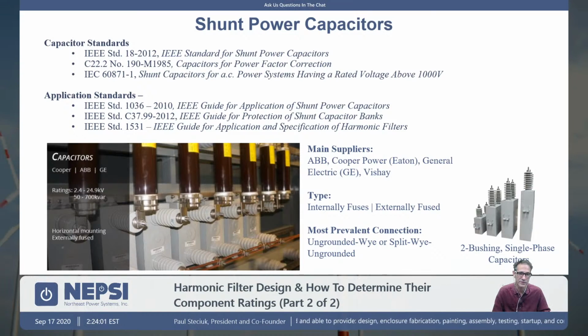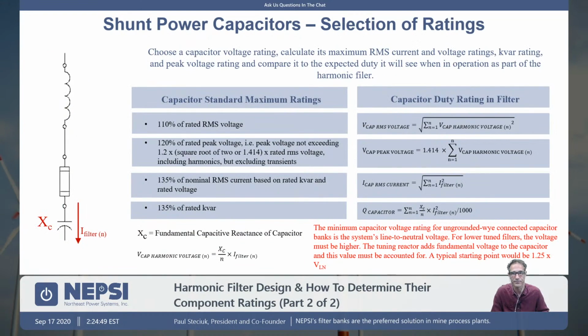The most prevalent connection for medium voltage, 2.4 kV through 38 kV, is an ungrounded Y capacitor bank, or an ungrounded split-wye capacitor bank. We won't really get into too much of what the difference between a split-wye and an ungrounded Y is, but they're both ungrounded, and that's really the key here. You would typically not want to connect a medium voltage capacitor to ground because it's introducing the zero sequence network into the system, and that's a more complex network. With your filter design, you'd now be dealing with the zero sequence network and the positive sequence network. So if we don't connect the filter bank to ground, we can ignore what's going on in that zero sequence network.